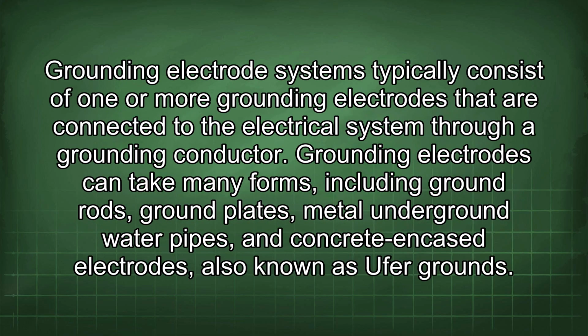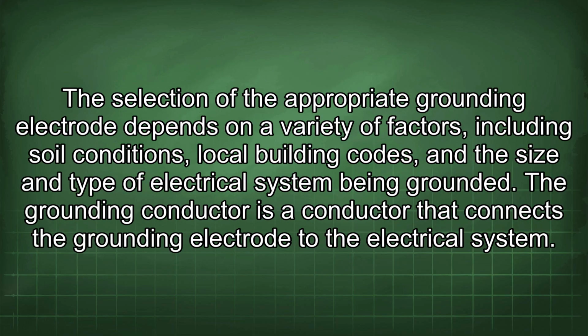Grounding electrode systems typically consist of one or more grounding electrodes that are connected to the electrical system through a grounding conductor. Grounding electrodes can take many forms, including ground rods, ground plates, metal underground water pipes, and concrete encased electrodes, also known as Ufer grounds. The selection of the appropriate grounding electrode depends on a variety of factors, including soil conditions, local building codes, and the size and type of electrical system being grounded.